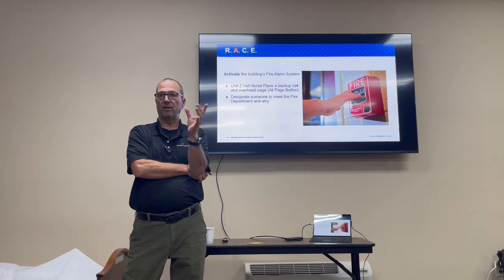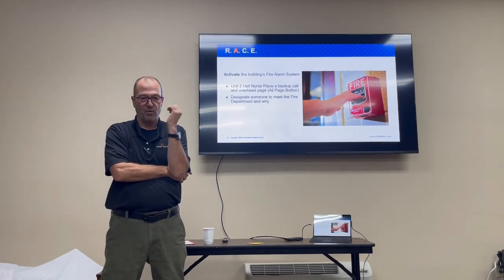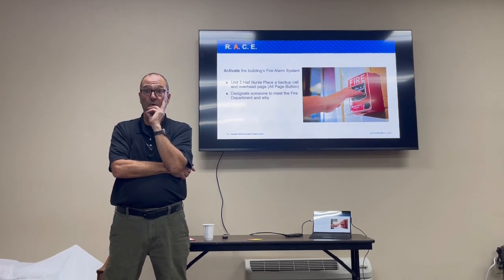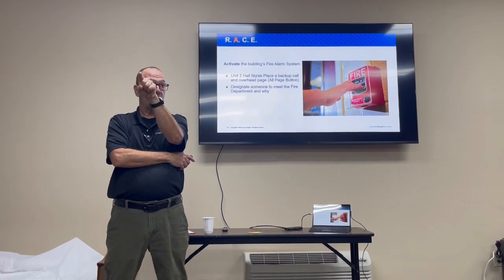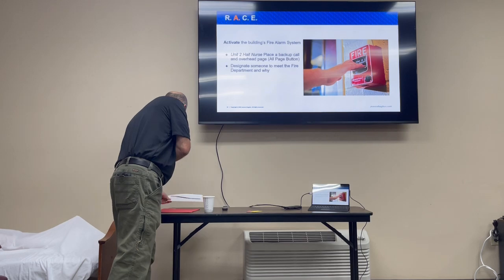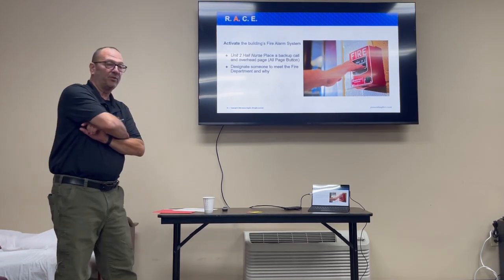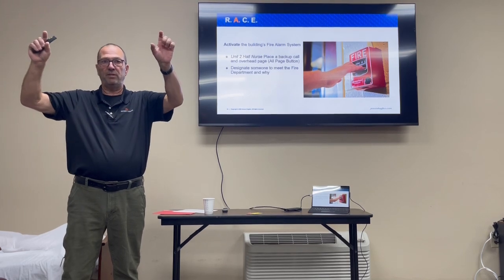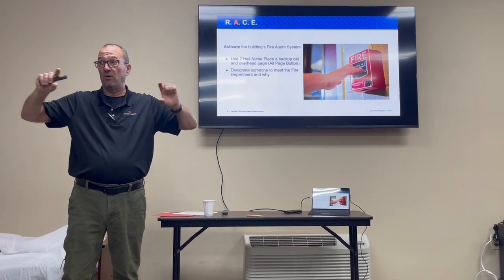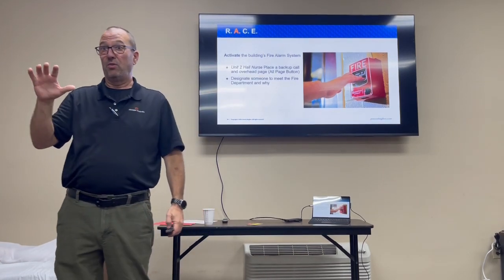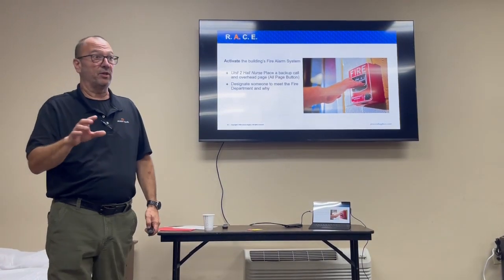Where else? If you hear the alarm going, you're at the nurse's station. You guys, there's an annunciator panel there. You can also go see where that fire is. It's going to show up where the alarm is. Okay. It will in the units. Well, there's 2 units anyway. That unit 3 for sure, and I believe there's one other unit that it won't say what room it is. It just says what zone it is. But the other units, it will say room 2, room 101 or where it is. So those are very good, and that's great when you can do that.